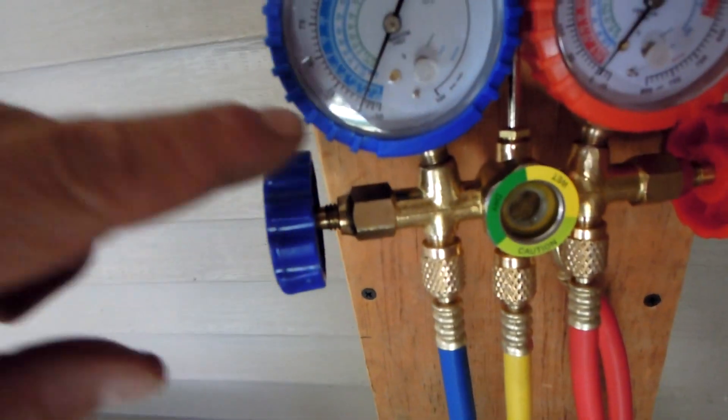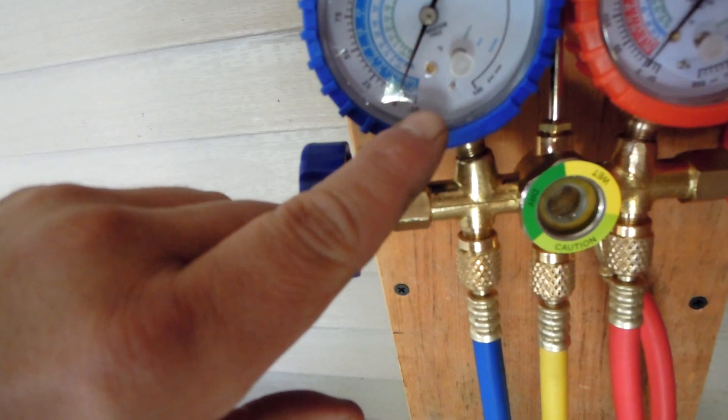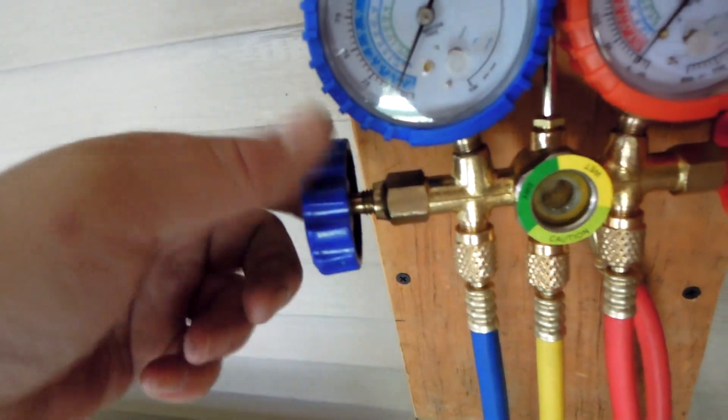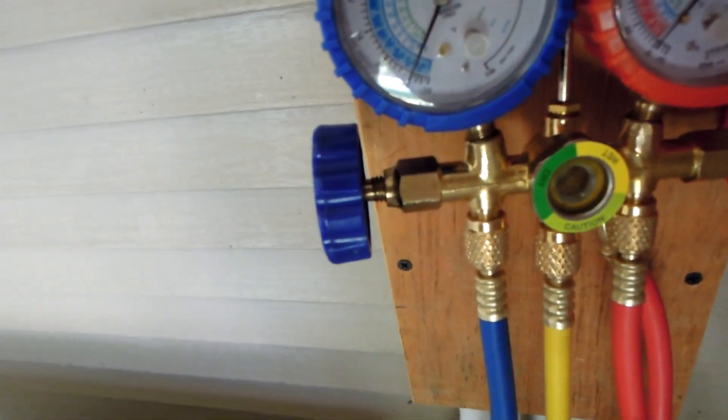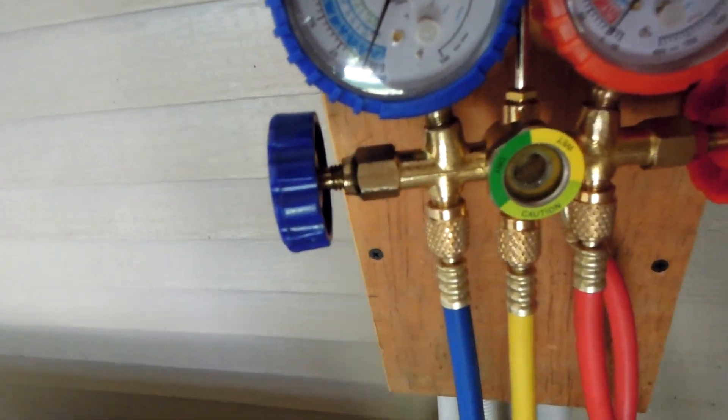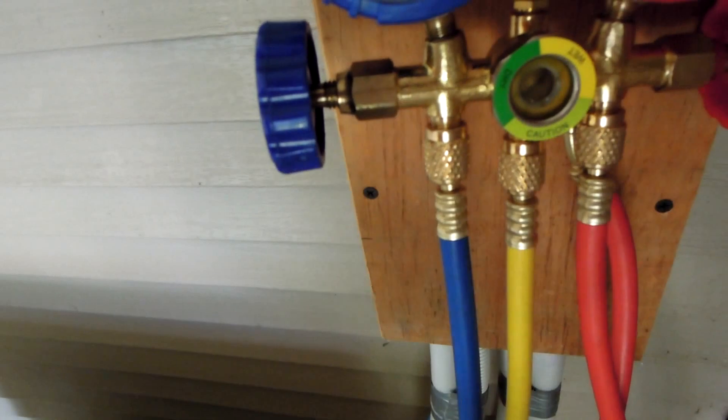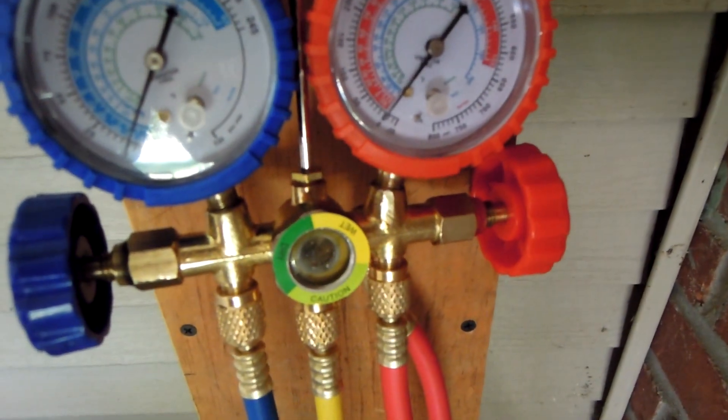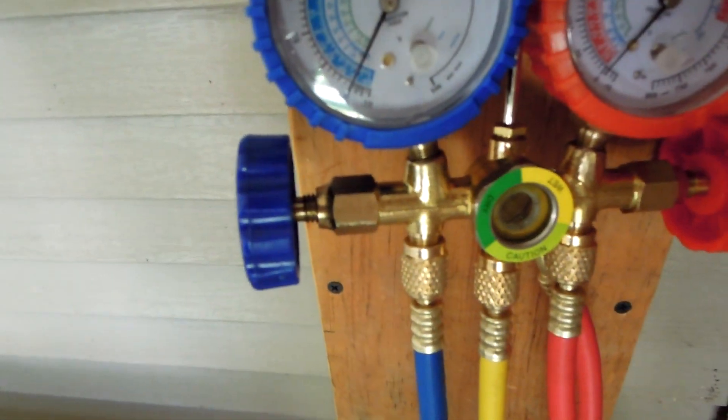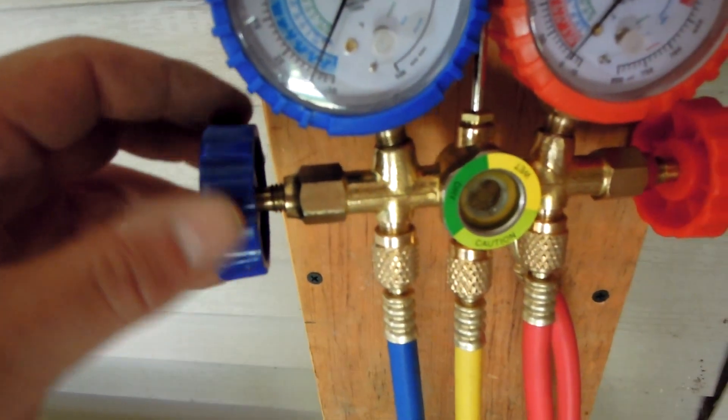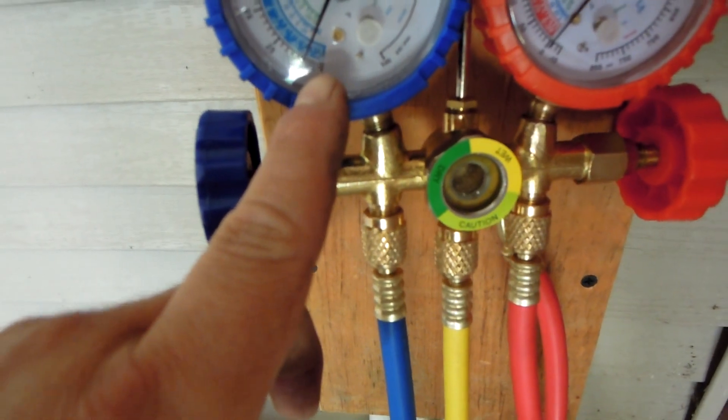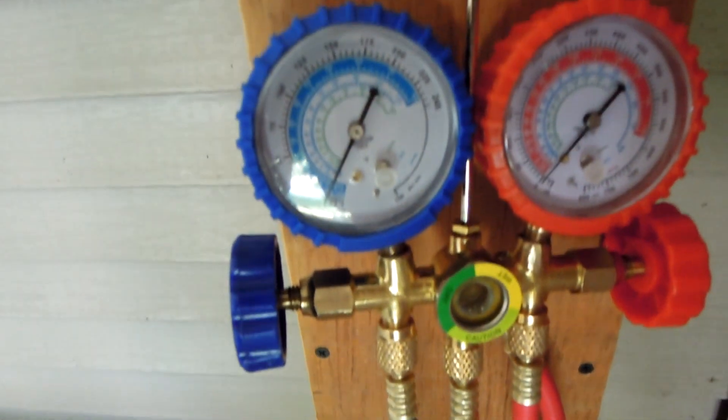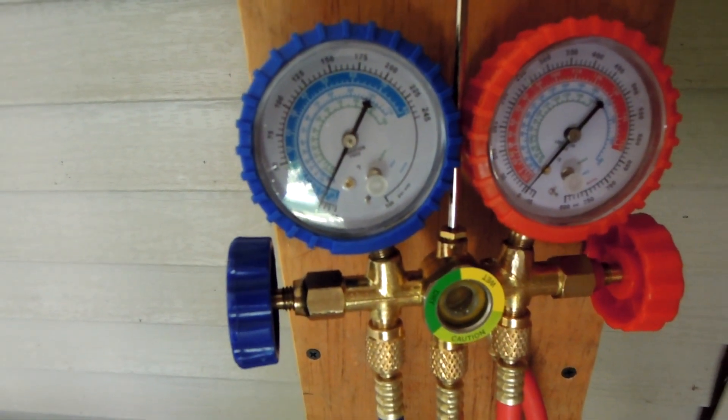And right here it should stay at negative 30. Make sure this valve is all the way open. This could stay closed because it doesn't really matter. And actually, definitely make sure that it's closed. The high side, nice and tight. So the low side all the way open. Make sure it gets down to negative 30. It'll probably take about 15 to 20 minutes. Let it sit.